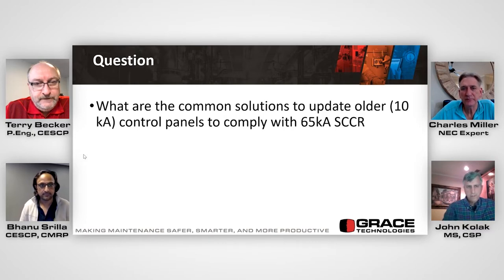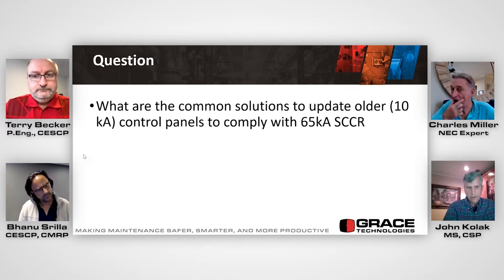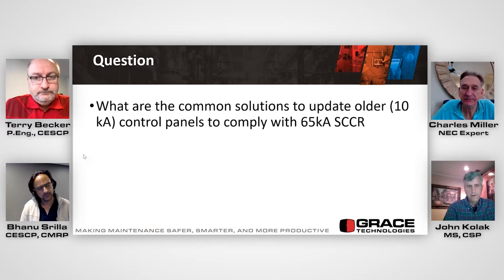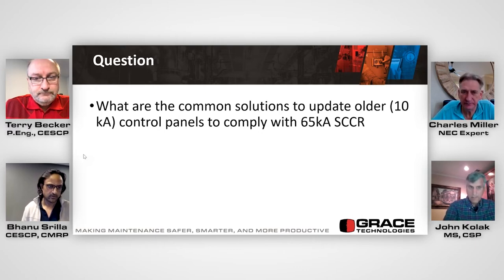Please remember these calculations are done on a system level. You're not just going to go to the next transformer and figure the bolted fault current; you've got to come up with the arcing fault current in that system. The whole system has to be modeled to capture that accurately. That's why we went away from the tables long ago, because we weren't getting the right information. So please understand, if you're going to come up with short circuit, particularly arcing fault current, you need to do that through system analysis.